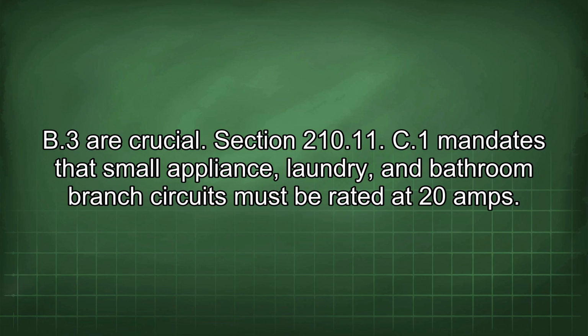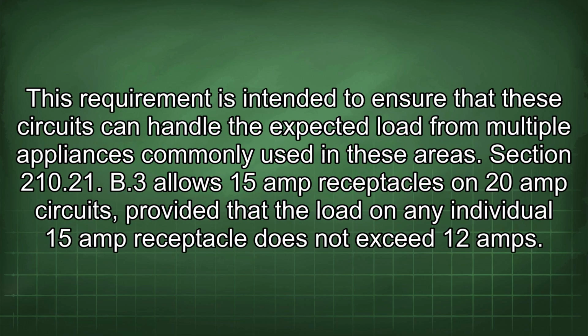Section 210.11(C)(1) mandates that small appliance, laundry, and bathroom branch circuits must be rated at 20 amps. This requirement is intended to ensure that these circuits can handle the expected load for multiple appliances commonly used in these areas. Section 210.21(B)(3) allows 15 amp receptacles on 20 amp circuits, provided that the load on any individual 15 amp receptacle does not exceed 12 amps.